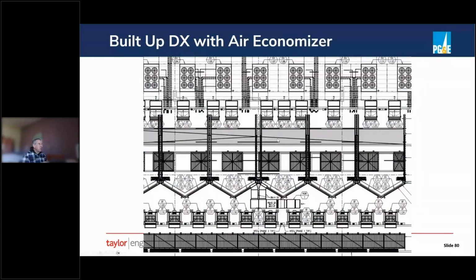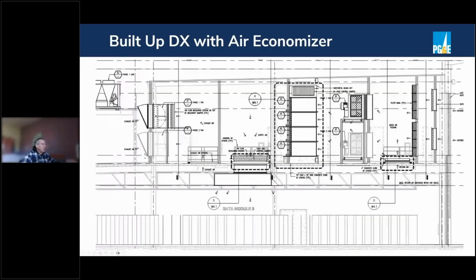All right. Another type of system is a built-up DX with an air economizer. Similar to packaged DX, this is building basically a huge mechanical room that has banks of cooling coils and banks of supply fans. Maybe I'll go to the next section. So here's a section view through that data center. And here's this built-up system, this huge 20-foot-high set of cooling coils served by a double-height bank of supply fans, with outside air on one side. One of the nice things about this is that we've set up the whole data center so that all the outside air comes in one side and all the exhaust air goes out the other side, so far away, blowing away. So this really is one of the better ways to deal with exhaust reentrainment, right? There was no exhaust reentrainment to speak of coming all the way around and back in this side.